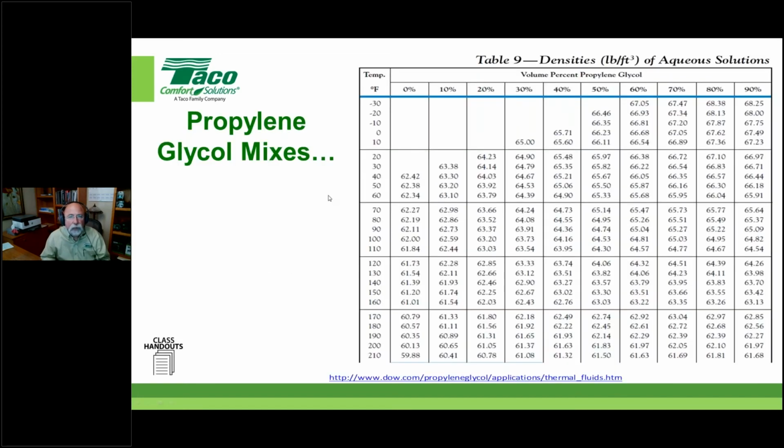I said that already. So let's look at fluid densities. I'm getting this from our good old folks at Dow Chemical. Whatever brand of glycol you folks use, this is where this came from. I'm not leaning on them any more than this is the same chart I've used for 20 some odd years. Let's look at the density because it's one way of determining some things. We have to solve for the density. Normally we'll take this and divide that out. Let's get a number to start with, because there's a temperature associated and a percentage of mixture of the glycol, in this case, propylene glycol.